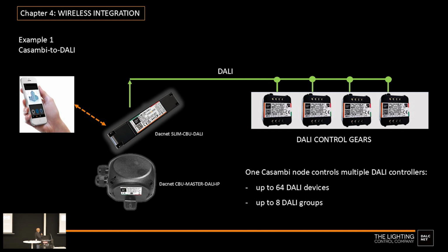Recently - something Casambi isn't promoting too much, but we saw with Kenny downstairs - Casambi has introduced the possibility to make the DALI group assignment directly from the app. In the past, the procedure was: I need the DALI programmer, program the DALI bus with different groups, and then connect to the Casambi device. Now you don't need the DALI programmer anymore - you simply connect the device, and through the Casambi app, you can identify the address, change the address, change the group, scan the bus, and get diagnostic information.